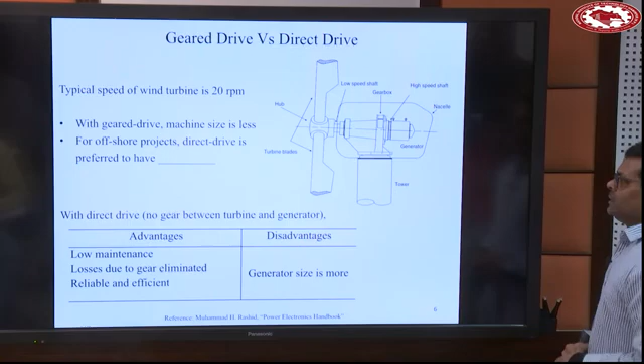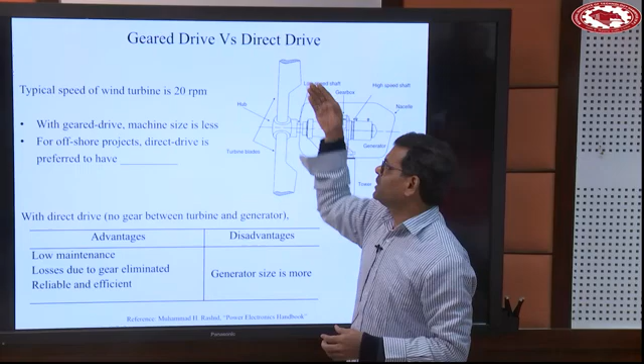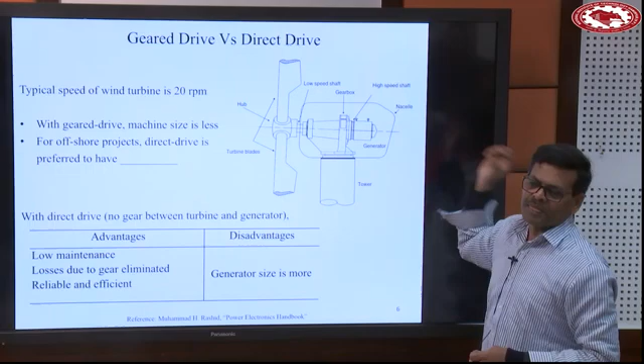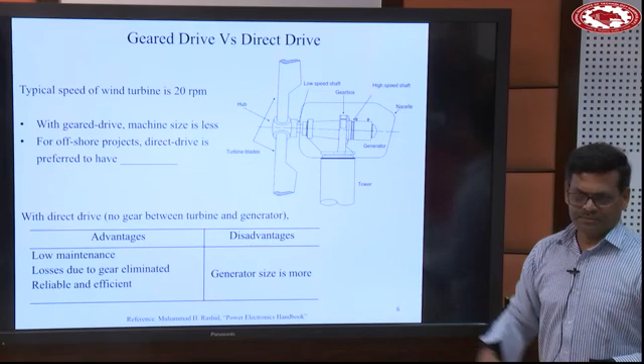But for offshore projects, where the windmill is installed in the sea, direct drive is preferred. Direct drive is without a gear system. If this is a 50 RPM windmill, the generator is also designed for 50 RPM. The reason is that efficiency, size, and cost are not considered here. What is considered is maintenance requirement. Suppose there is a breakdown, how quickly can you attend to the problem? Going to the sea and doing the rectification will take a huge amount of time. So considering that requirement for offshore projects, the gear system is eliminated, and therefore we have to go for a low speed generator.